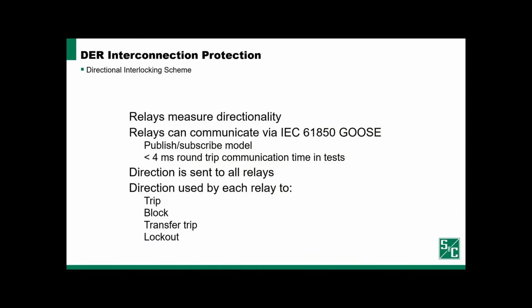Another approach or technique that's quite useful in microgrid and distributed energy resource integrated systems is directional interlocking schemes. These schemes will involve relays measuring directionality of the current, as I described earlier. And the relays can communicate with one another. A typical way that we've used is IEC 61850 GOOSE messaging. And GOOSE is particularly useful for two major reasons. One is because of the publish subscribe model. It enables one device to communicate with many other devices straightforwardly, which is useful in complex system topologies that microgrids often include, and DER penetrated systems often include.